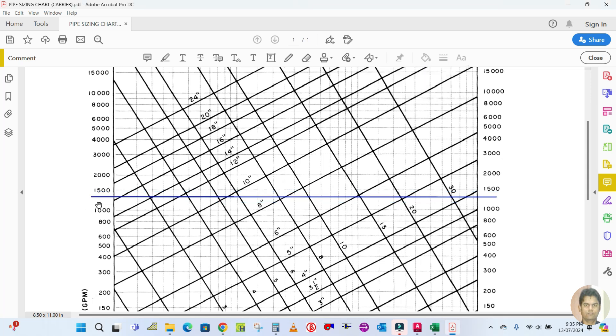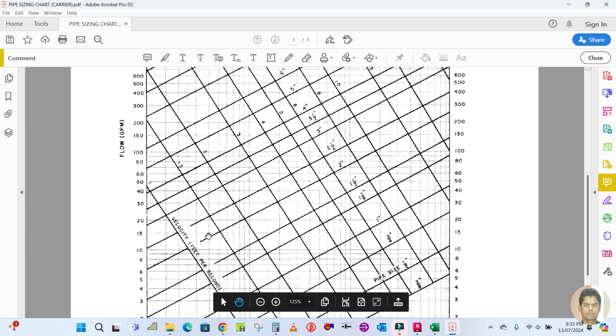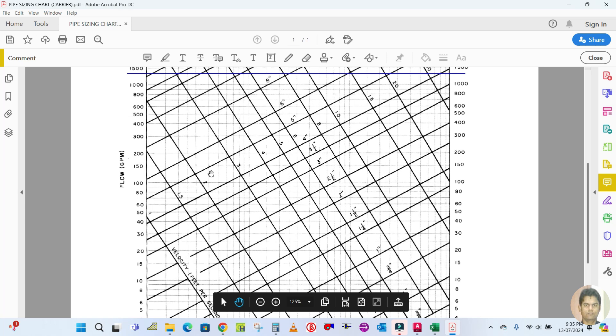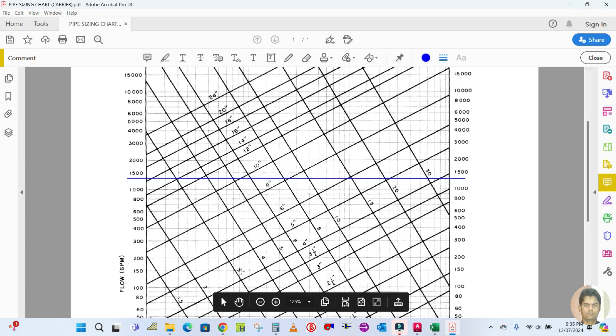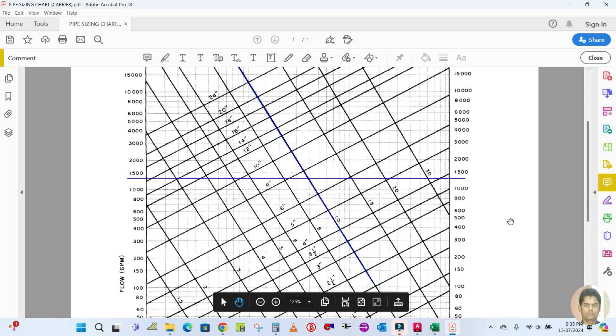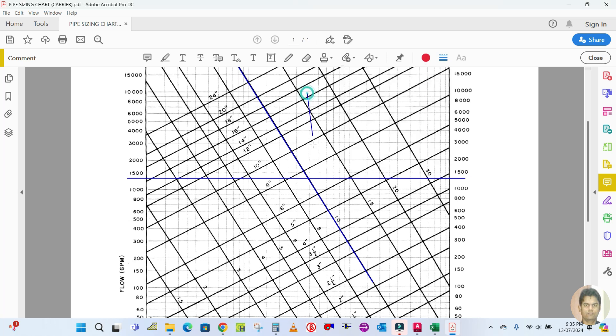I've drawn the line at 1440 GPM. Next is velocity. The inclined lines on the chart represent velocity in feet per second. Our velocity is 10 feet per second. I'll draw a line parallel to the 10 feet per second velocity line on the chart.